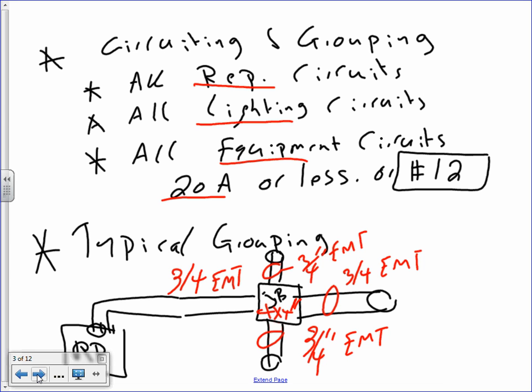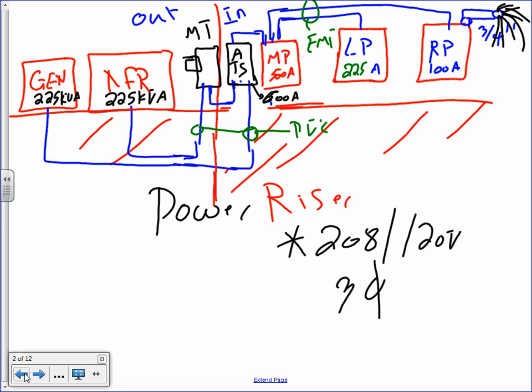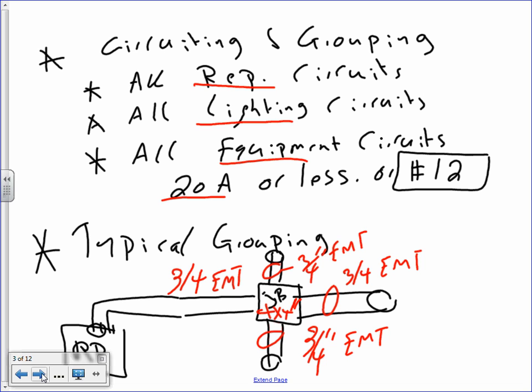Can I have thumbs up? We understand that, Chad? Cool. Same thing for lights, the lighting panel. So go back here. When you have your lighting panel, you take a tiny little conduit here, 3/4 of an inch, and you feed all your lights by grouping the 20 amp circuits coming out of it. Cool? And in my judgment, if you have dedicated equipment circuits, guys, also group them. For example, a vending machine needs a dedicated circuit. Also group them, put them in the same conduit.